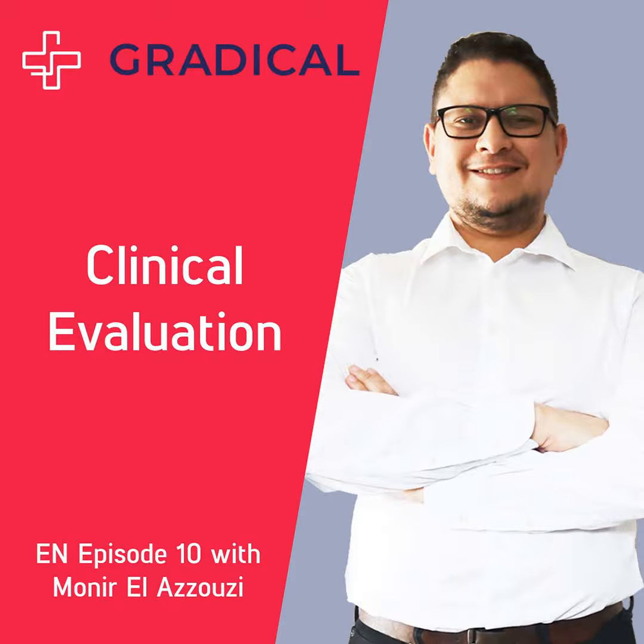Can you justify or have some proof that even if the material is different, it's working the same, interacting the same, leachables are the same, extractables are the same, etc.? And then maybe, I cannot say for sure, but maybe you can go with that to the notified body. And here, the last part is to do the biological evaluation and prove that it's biologically safe according to, let's say, ISO 10993.